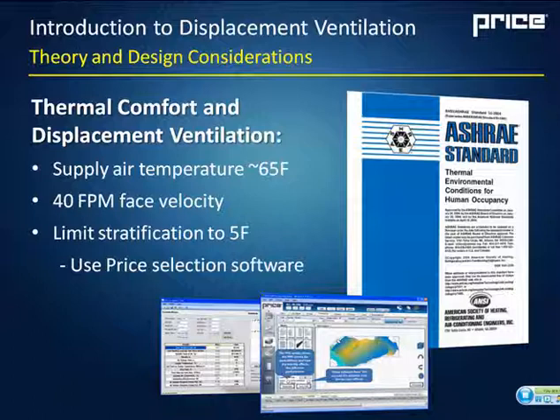Another question with displacement ventilation is, with the cool air moving along the floor, what about thermal comfort for people who are in shorts or skirts or open-toed shoes and things like that? So the first point is that the supply air temperature is actually much warmer than we are used to with traditional air conditioning systems. Whereas with a traditional system we would be using 55-degree air, with a displacement system we're using 10-degree warmer air, about 65 degrees. So it's not far from room temperature.